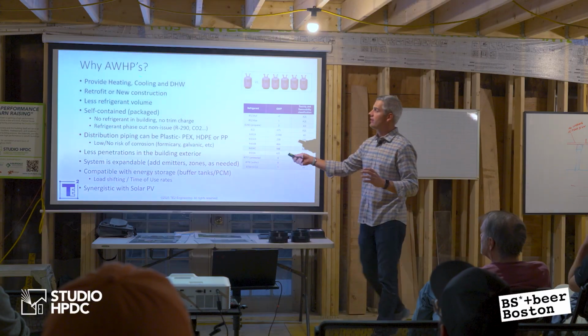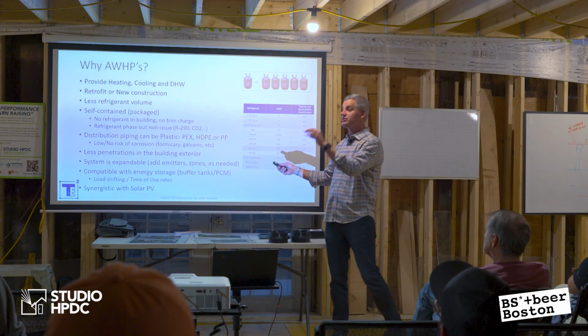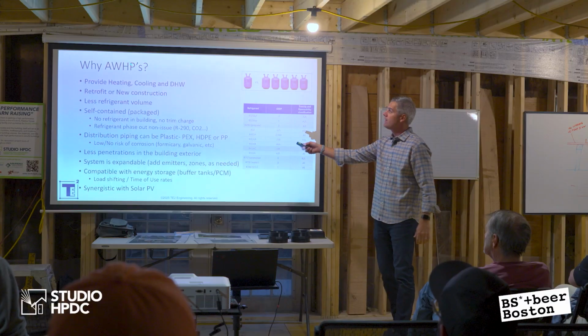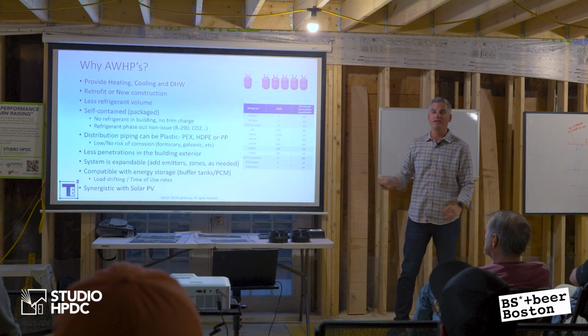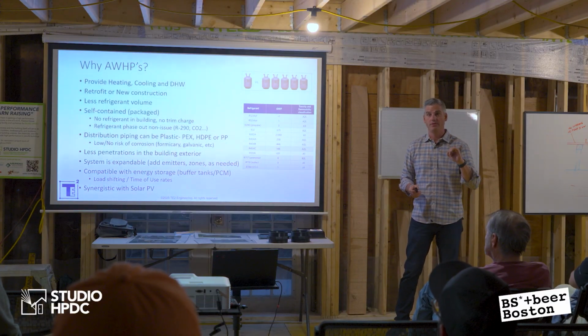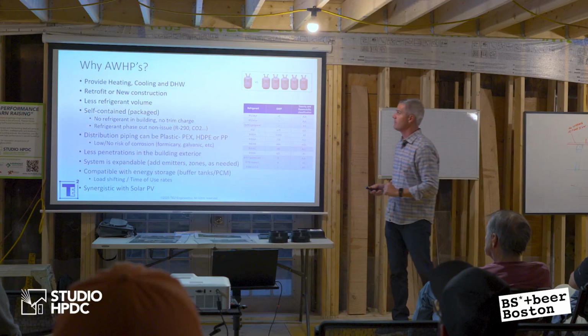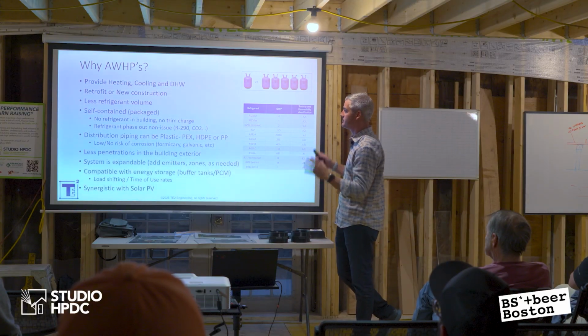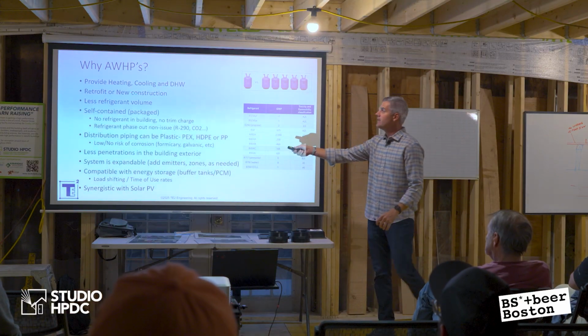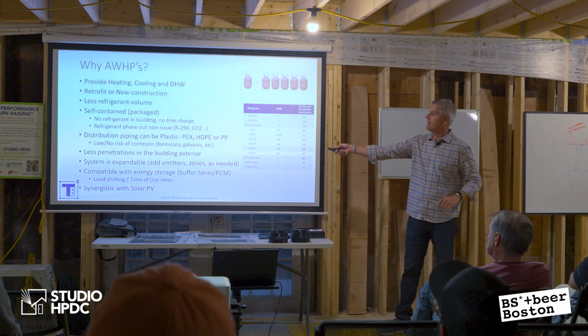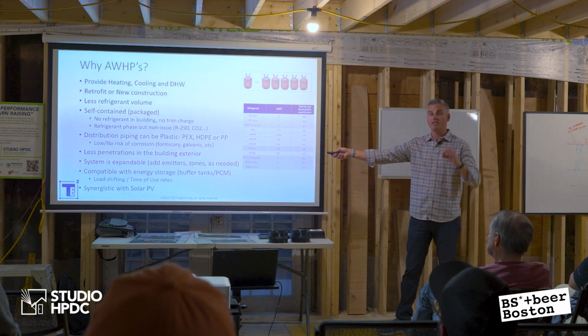And so the reason we like air-to-water heat pumps is for a bunch of the reasons that Michael mentioned and some more. So first off, with air-to-water heat pumps, I can provide heating, cooling, and domestic hot water. I can do all three. Right? I get a 3-for-1 with that approach. I get heating, cooling, and DHW. It's a magic box outside that does all three. I can do it in retrofit and new construction. We'll talk about that. It's less refrigerant volume. That's a big one compared to VRF right off the get-go.